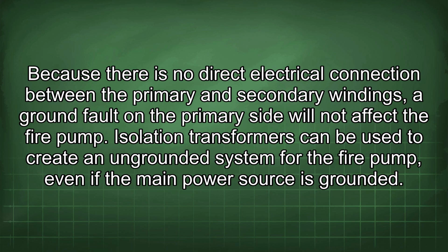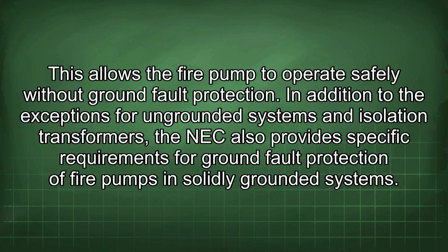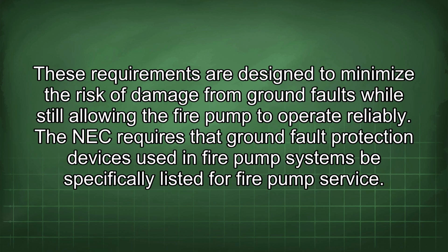Isolation transformers can be used to create an ungrounded system for the fire pump, even if the main power source is grounded. This allows the fire pump to operate safely without ground fault protection. In addition to the exceptions for ungrounded systems and isolation transformers, the NEC also provides specific requirements for ground fault protection of fire pumps in solidly grounded systems. These requirements are designed to minimize the risk of damage from ground faults while still allowing the fire pump to operate reliably.